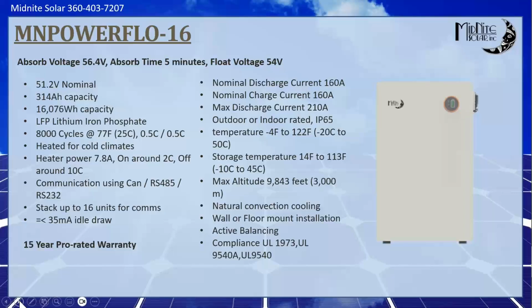So just keep that in mind when you're sizing that system, that 160 amp area is kind of where you want to be. You don't always want to be pushing it to 210 all the time. I did say outdoor rated IP65. We do rate this one down to -4 degrees Fahrenheit with the heaters, and storage again down to 14 degrees Fahrenheit, which sounds kind of weird, that you can set it outside at -4, but you can only store it at 14. But that's got to do with the heaters.